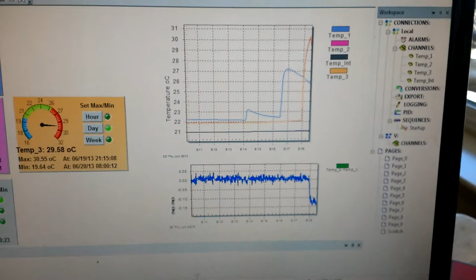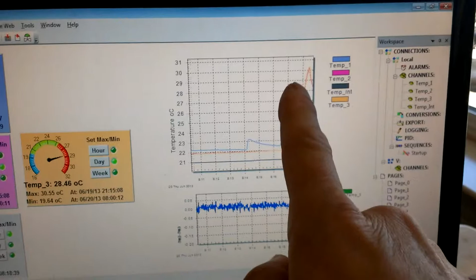You can see I'm getting a dip down here in the blue trace. The dip is the difference between the two. Since there is a little difference in response rate, you get a bigger deviation between the two when they're changing. Now they're cooling back down, and the rate of change is going to start to decrease, and you'll see we'll lose this deviation between the two. But at equilibrium, the deviation between the two thermocouples is amazing. It's on the order of 0.02 degrees Celsius, and the response rates are very even.